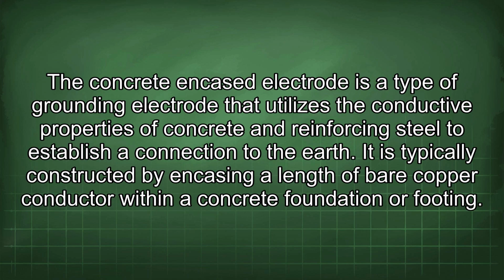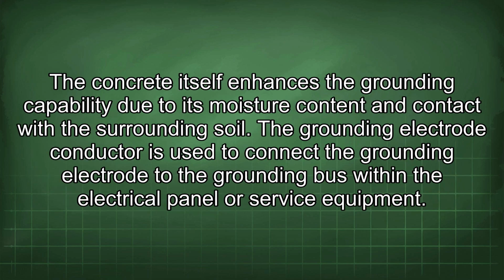A concrete encased electrode is a type of grounding electrode that utilizes the conductive properties of concrete and reinforcing steel to establish a connection to the earth. It is typically constructed by encasing a length of bare copper conductor within a concrete foundation or footing. The concrete itself enhances the grounding capability due to its moisture content and contact with the surrounding soil.